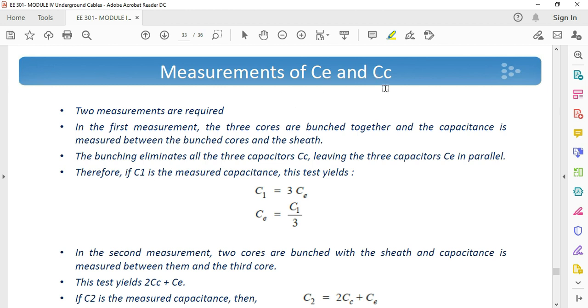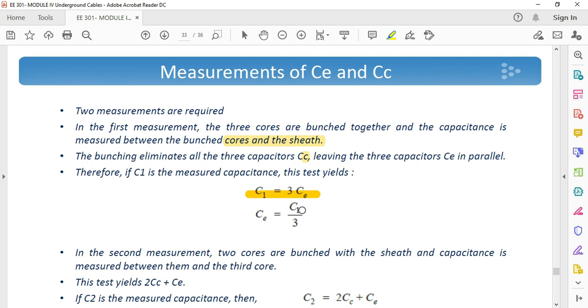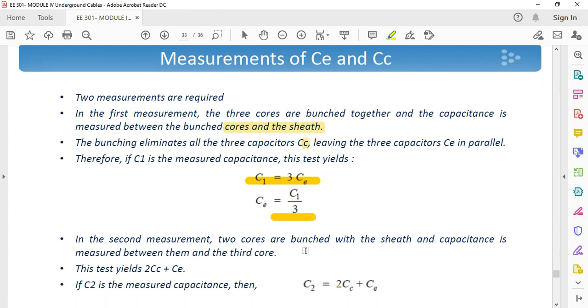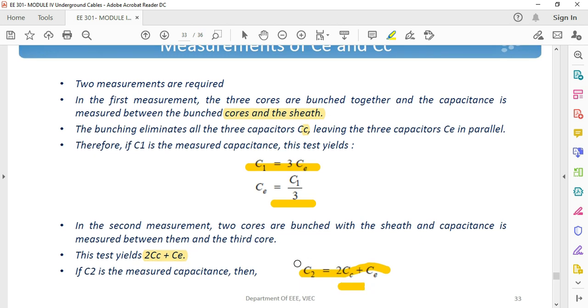We can measure the values of CE and CC using two measurements. In the first measurement, three cores are bunched together and capacitance is measured between the cores and the sheath. Bunching eliminates all CC capacitors, leaving three CE in parallel, so C1 = 3CE, giving CE = C1/3. In the second measurement, two cores are bunched with the sheath and capacitance is measured between the conductors, giving C2 = 2CC + CE. Since CE is already known, we can find CC from C2.